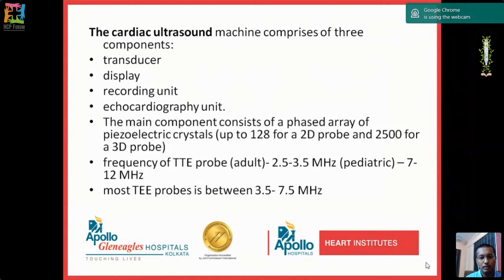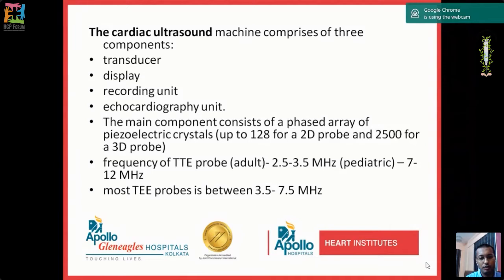The echocardiography unit consists of three main components: the transducer, display, and recording unit. The phased array emitted by piezoelectric crystals — up to 128 for a 2D probe and 2500 for a 3D probe. The frequency of transthoracic echo probe for adults is around 2.5 to 3.5 MHz, for pediatric use it is around 7 to 12 MHz, and transesophageal echo probes use between 3.5 to 7.5 MHz.